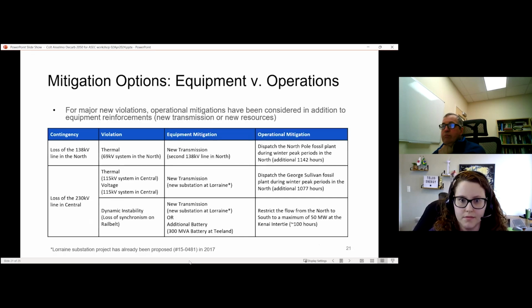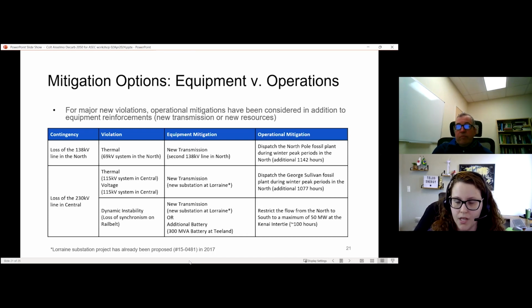Next slide, please. Because for this contingency we saw that we could have different options, we decided to check different options for other major problems we saw during our analysis as well, something that we didn't do for the other scenarios. Here are some examples. For example, there are a lot of thermal overloads in the north on the 69 kV system when we lose a particular 138 kV line in the area. And we can solve that with a new big transmission project.